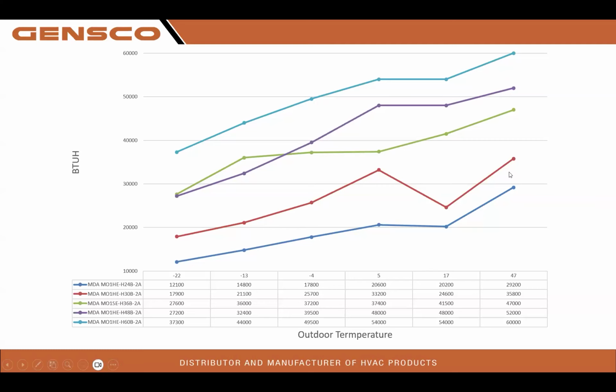Also, you'll notice on the 2-ton model this gradual dip starting at 47 degrees, dropping down to 17 degrees. This is actually inaccurate. This curve is actually drooping across this way, okay? So don't let the 2-ton model distract you here. This is a typo, basically, okay? And notice clear down at -13 degrees, we are still producing 36,000 BTUs on the 3-ton model. On the 5-ton model, we are still producing 44,000 BTUs. Big performance.